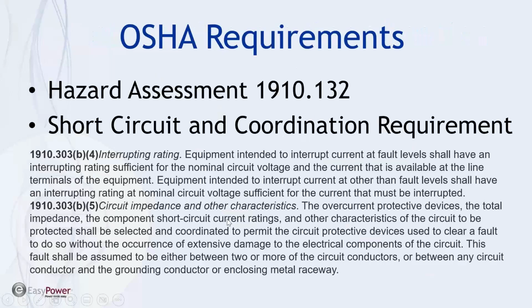Okay, so here's the OSHA stuff. Number one, there was a question: does OSHA require that a short circuit study or an arc flash study be done? It started off with an arc flash study. OSHA 1910.132, subpart I, the personal protective equipment section, has nothing on arc flash clothing and that kind of thing. The only place it has that is in the utility standard. However, the electrical standard, subpart S, still refers to NFPA 70E.